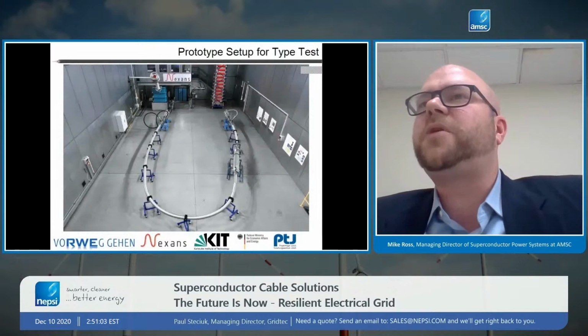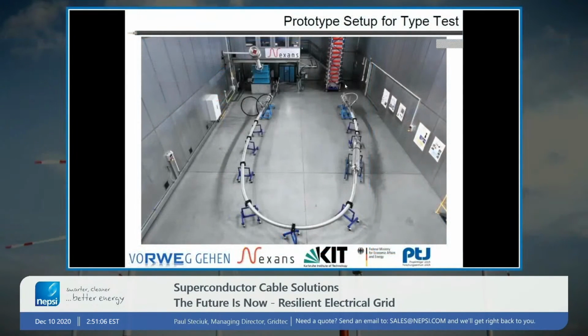Here's a couple of pictures from this project. So this is the type testing of the cable. So every superconductor cable today is a bit different. We haven't hit the point yet where we're making the same cable over and over again. So we run a lot of tests because each design is new, called type tests. And a type test involves a 40-meter cable, 2 terminations, and a splice. And so this is installed inside this test chamber, and then a whole battery of tests are run on the cables. So standards exist in IEC and CIGRE for the testing of superconductor cables. And so those are standards that the utilities run down, and they explain how to test the cables in order to prove that the design is going to work properly. So this is done for every cable today.